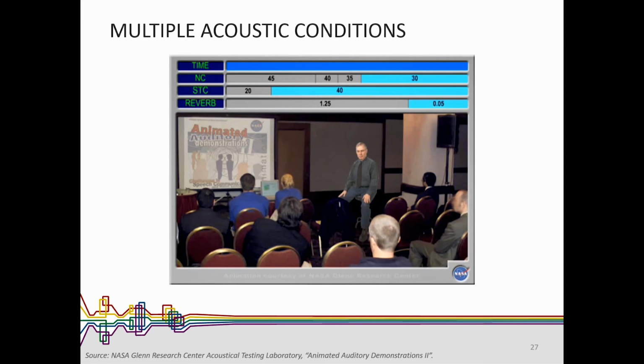Well, the ratings for all those VAV boxes assume it's above a ceiling. So now you have to do the math to figure out what happens if it's not above a ceiling. You've got to do some other things like that. So while that's a good start, there are a lot of other sources that can create noise in your space. David will be doing a short demo on NC calculations, just showing what goes into it.